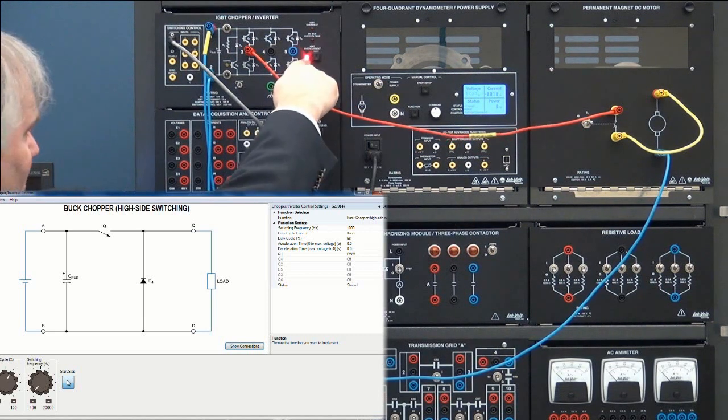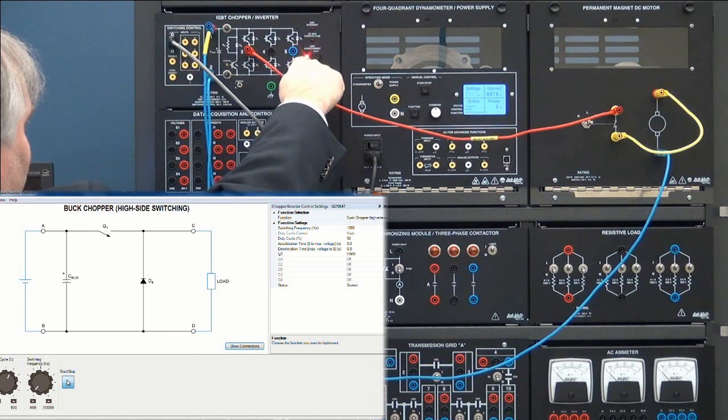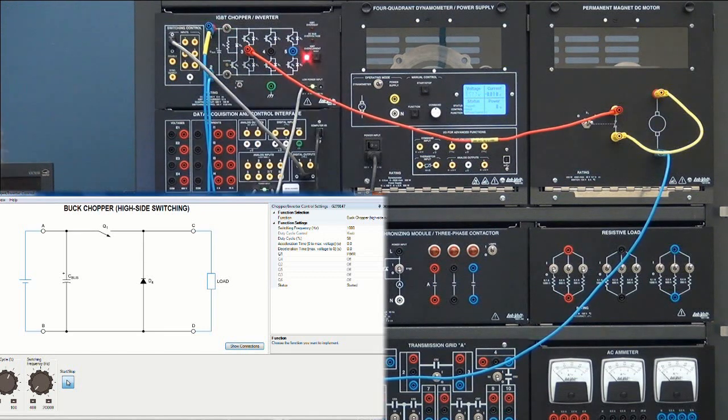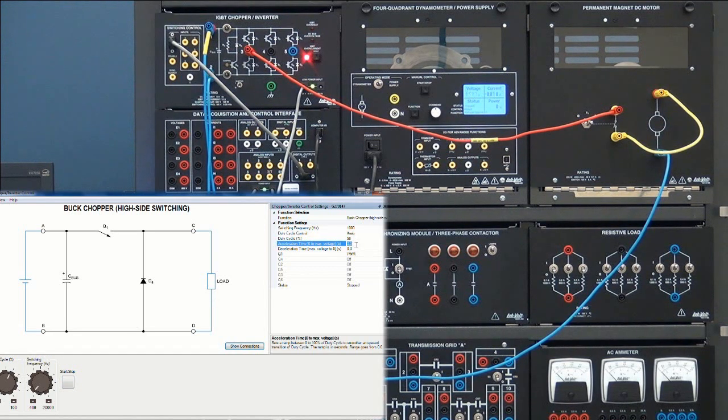The worst that could happen is that you would go into over current if you try to go to a high speed at once. In that case I want to stop here and maybe put some acceleration time to avoid going into over current. Let's say I put five seconds for acceleration and five for deceleration.